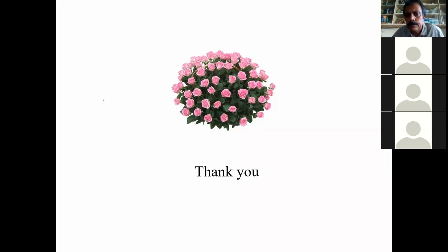Okay, next. Sir, what are different types of sensors available to feedback the pump operation with VFD in an auto loop? Yeah, that's why you have a pressure controller, temperature controller. You can even have a flow controller. It all depends on what your requirement is, what your process is, what needs to be controlled. Sensors are available for anything. The only thing is you need to identify what needs to be controlled and what is the range that you want. Accordingly, you can give a feedback to the VFD.